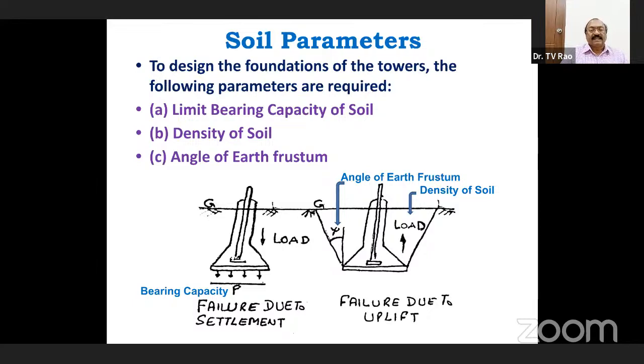Dead weight of the structure is very less, and compression due to wind force will also be considered, and the failure due to settlement will be checked for the bearing capacity of the soil. So mainly the towers fail due to uprooting of the tower, due to wind forces only.